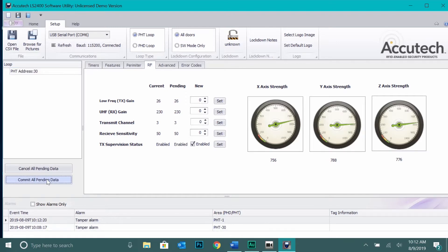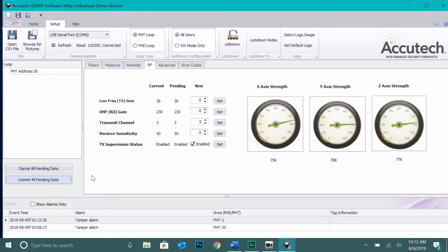Next, we will cover changing the frequency of the door controller. This is necessary when two or more door controllers are in close proximity of each other, as a tag from one zone can trigger an alarm in a different zone. This is what we call crosstalk.